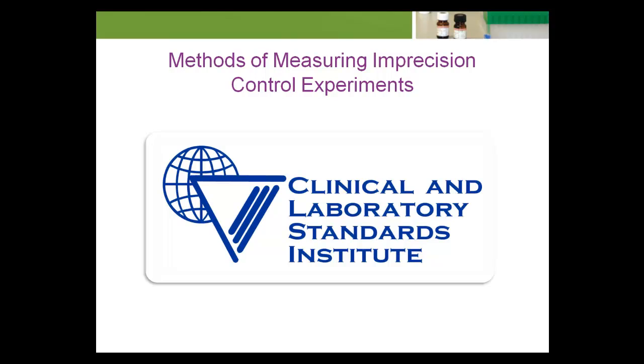Another method is to perform more formal testing by following one of two Clinical and Laboratory Standards Institute (CLSI) standards: EP5-A2, Evaluation of Precision Performance of Quantitative Measurement Methods, and EP15-A, User Demonstration of Performance for Precision and Accuracy. Both standards describe protocols for controlled experiments used primarily to verify that the laboratory can meet the manufacturer's claim for precision.